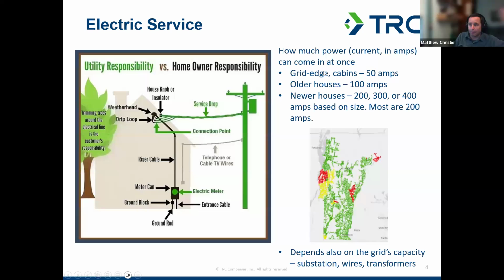Grid edge homes, way out in the back, very old homes and cabins, might be on 50 amps or 60 amps of service. This is called your electric service limit, a measurement of how much power can flow across this wire and through your panel. Older houses might have 100 amps, which was very common up until the 90s or 80s depending on where you lived. Newer houses are all on 200, 300, or 400 amp service. Most are on 200 amps these days, but bigger houses will be on 300 or 400, and a commercial entity might be way higher than that, 800 or more. They even get into three-phase power and other things we're not going to talk about.